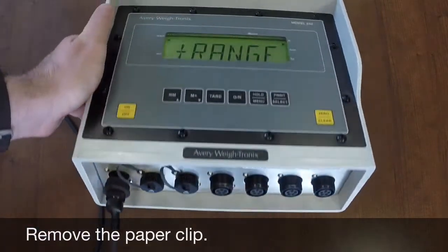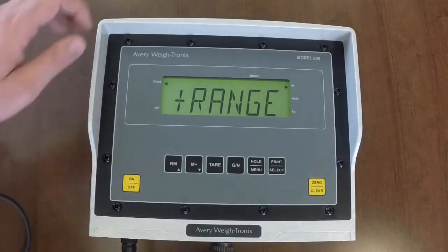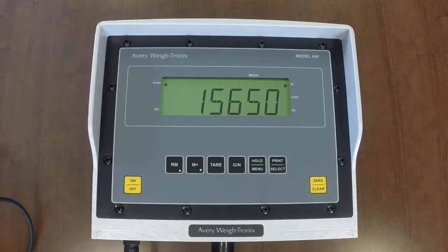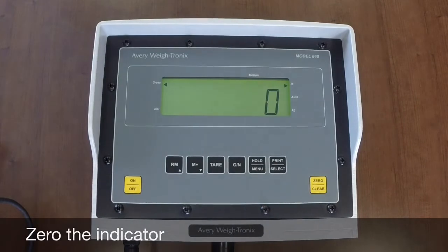Connect one of the way bars into the indicator. If you are utilizing a junction box, connect the junction box cable into the indicator, and then connect one weigh bar into the junction box. Zero out the indicator. The indicator should stay stable at or near zero. If it drifts, says plus range or minus range, or displays an error, check the cable for the weigh bar for any bad spots. Repair the cable as necessary by removing the bad spot and splicing the connection. If the weigh bar continues to have issues, contact Scaletech for further guidance.